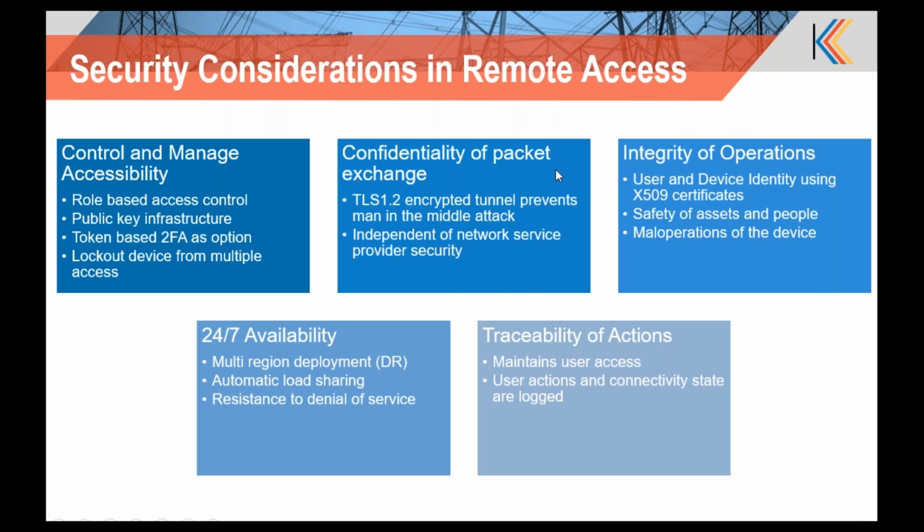And talking about confidentiality, this is a TLS 1.2 tunnel, an encrypted tunnel created from the field devices and also from the engineering PC. Thereby, it prevents man in the middle or data spoofing at any part of the network. It's also independent of the network service provider security, so we don't need to rely on the internet service providers, VPN, or any other security measures. It takes care of the end-to-end from the device up to the engineering PC. Connections are secured with the TLS 1.2 tunnel.